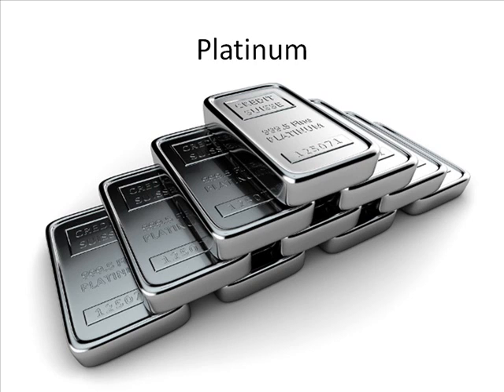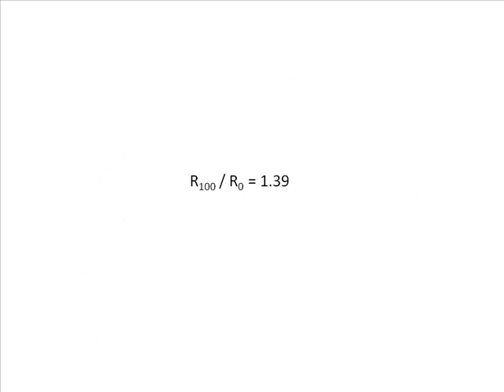This is done by measuring the resistance of the platinum at 100 degrees centigrade and the resistance of same platinum at 0 degrees centigrade. For pure platinum, the ratio of these two resistance values would be 1.39.